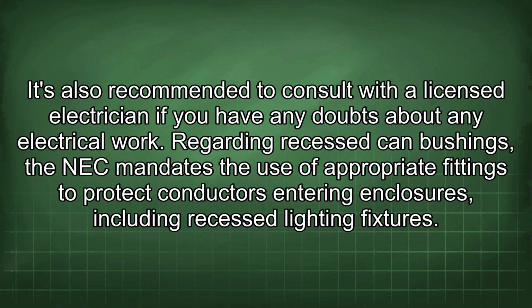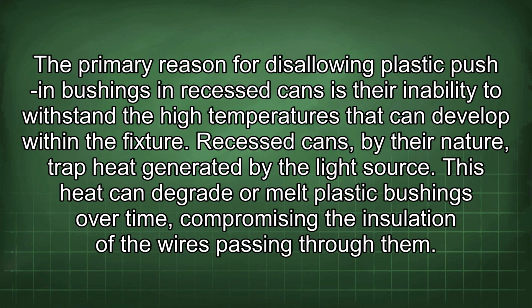Regarding recessed can bushings, the NEC mandates the use of appropriate fittings to protect conductors entering enclosures, including recessed lighting fixtures. The primary reason for disallowing plastic push-in bushings in recessed cans is their inability to withstand the high temperatures that can develop within the fixture. Recessed cans, by their nature, trap heat generated by the light source. This heat can degrade or melt plastic bushings over time, compromising the insulation of the wires passing through them.